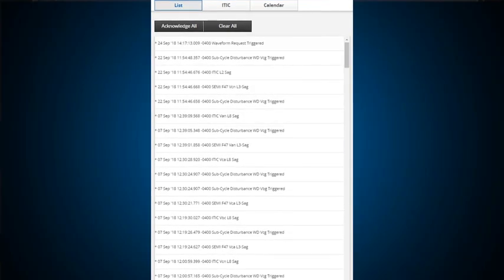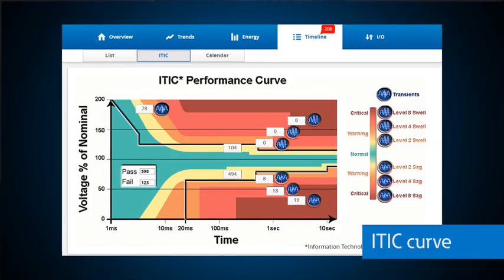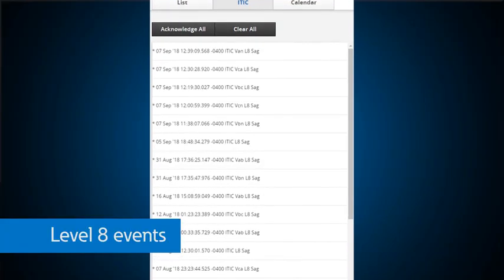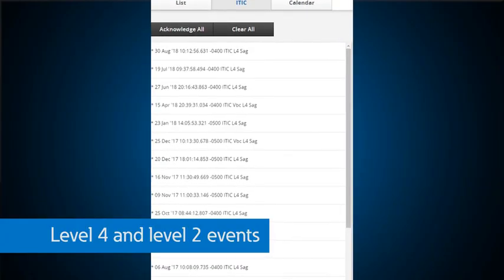Let's say you were called in to troubleshoot why a system malfunctioned. You aren't sure of the cause, but you wanted to eliminate power as a cause. While you can search a long list of logged events looking for a smoking gun, you can more easily sort event data by two methods on the power expert meter: the ITIC curve and the event calendar. In the power expert 6000 and 8000, the automatic ITIC curve generation calculates the time-magnitude correlation and plots all the events that have occurred on your power system. From there, you can sort to look at the data from the worst events first — what the power expert meter classifies as level 8 events — all the way down to other events that may or may not cause problems, what we call level 4 and level 2 events.